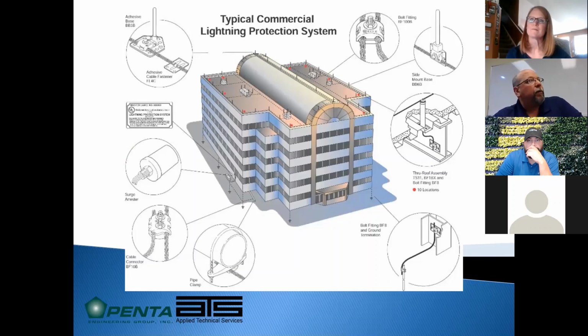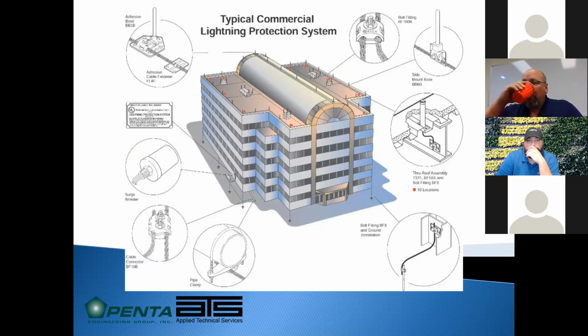The typical commercial lightning protection system might look something like this. This is laid out in accordance with NFPA and UL. And we have air terminals. There are basically three names: air terminals, strike termination devices, and lightning rods. All generally mean the same thing. And so depending on the height of the air terminal, these are spaced either 20 or 25 feet apart. They're interconnected with a conductor cable that maintains a downward or horizontal path.